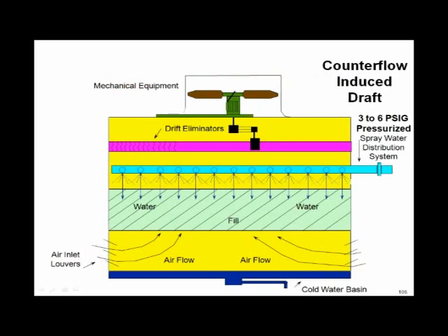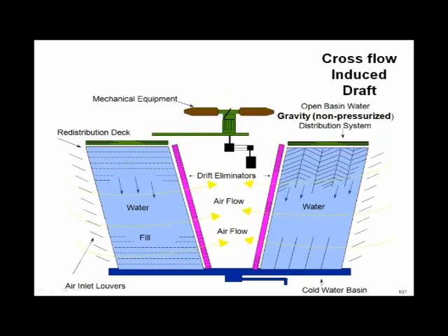Ladies and gentlemen, this is a counterflow tower with the pressure drop. You see the spray nozzles through it, and the air is coming from the bottom going up. Water's coming from the top down, so therefore it's called counterflow. This is a piping seminar. What we're trying to teach you is where you put that 3 to 6 pounds of pressure: into your pump head loss calculation. Just that simple. In a crossflow tower, you do have hot water distribution, with hot water basins and just gravity flow. So you don't need the extra 3 to 6 pounds there because gravity takes care of it.